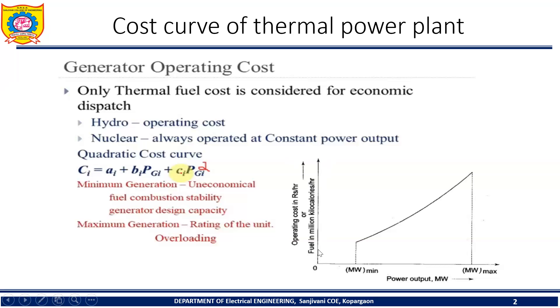This is shown in the cost curve. The cost Ci for the i-th unit is given by the quadratic equation: Ci = Ai + Bi·Pgi + Ci·Pgi², where Pgi is the generator power output of the i-th unit, and Ai, Bi, Ci are constants. This is the cost curve of a thermal power plant.